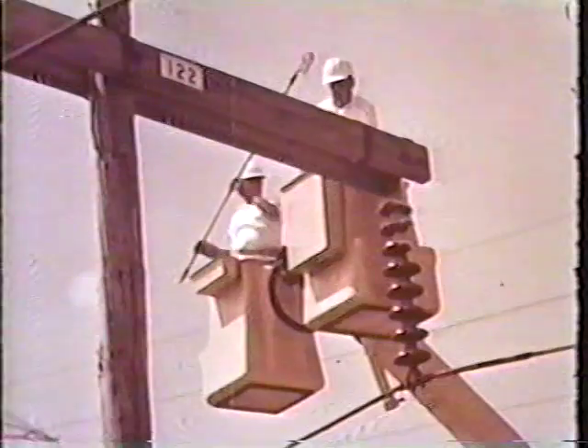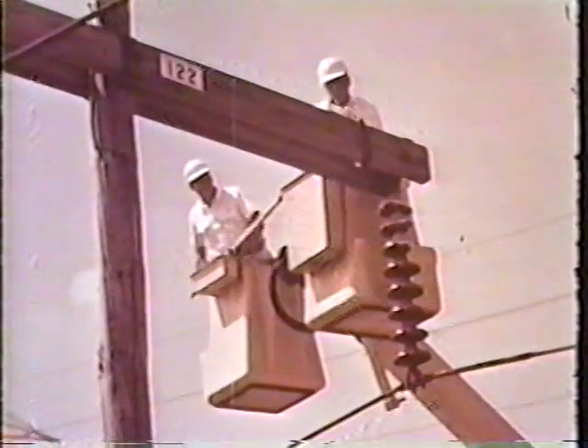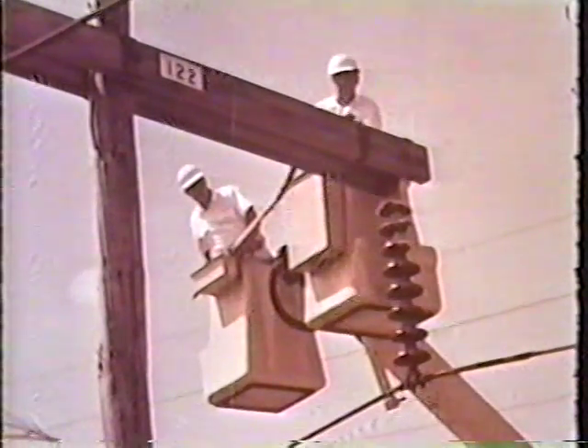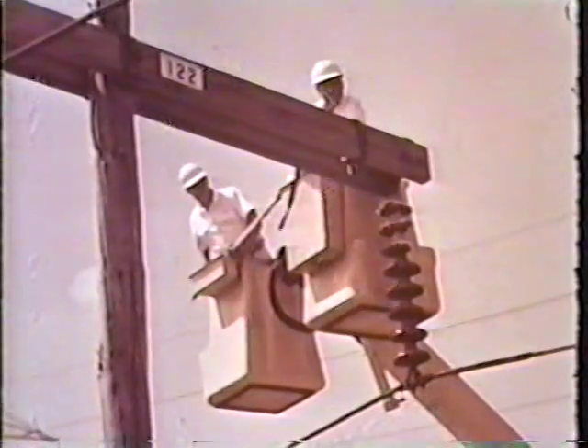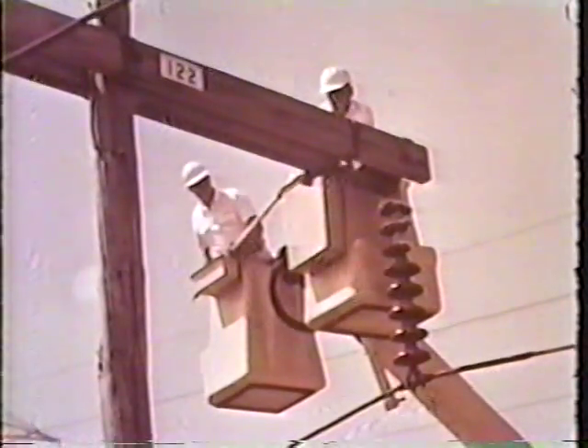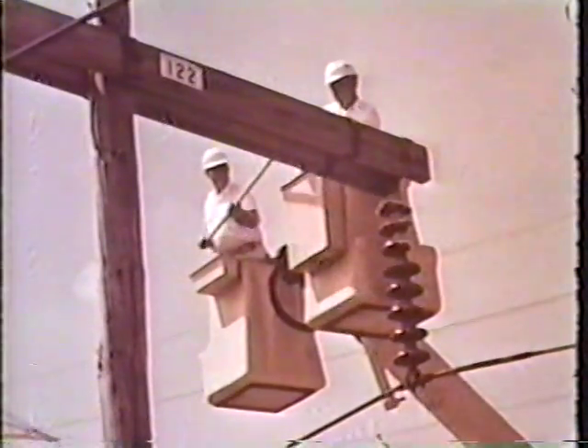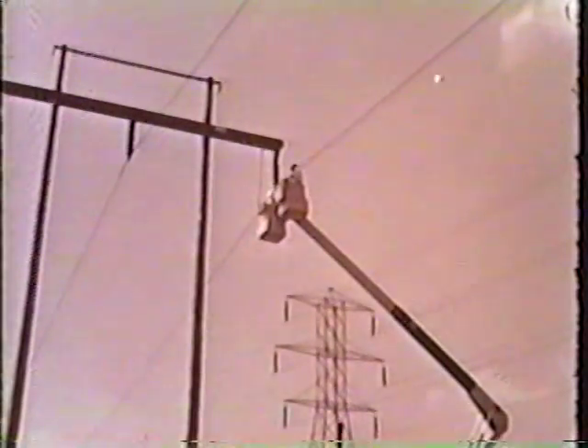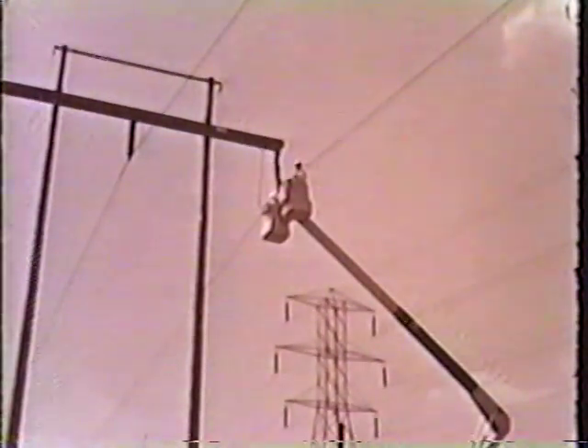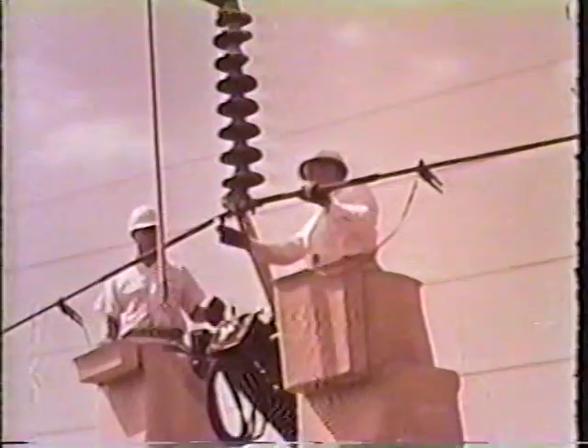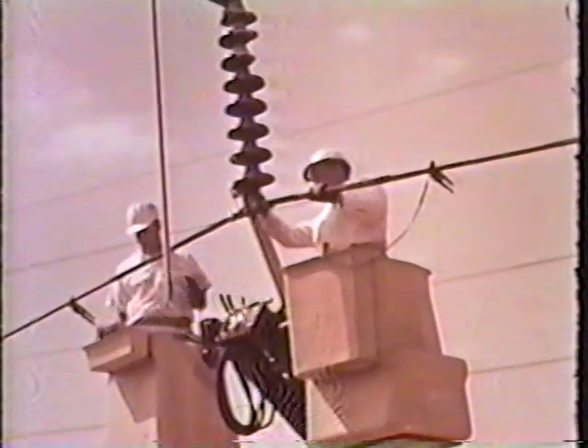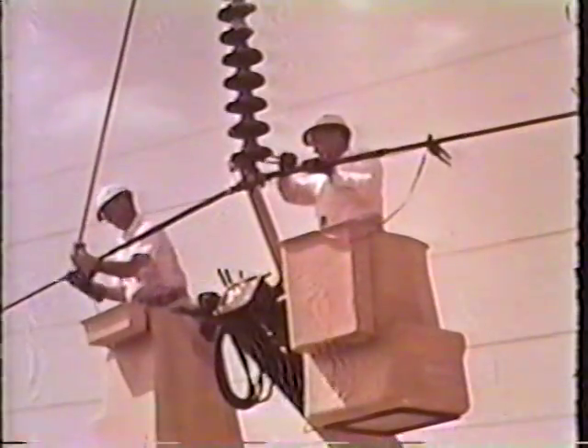The crew ascends to the cross arm, checking the structure carefully for hazards on the way up. A link stick is attached, and then the buckets are lowered to conductor height. After bonding leads are attached, the conductor is lifted slightly to slack off the insulator string.